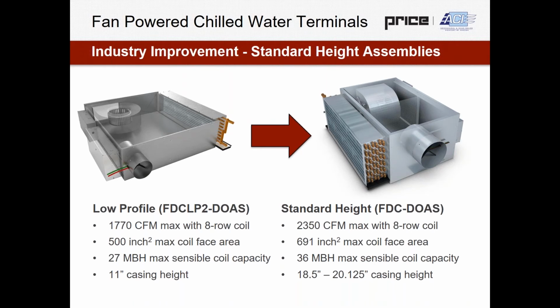For those of you who maybe aren't familiar with the history of this equipment, it was originally established and created for the Washington, D.C. region, which has some really strict building codes, especially in regards to building height. Nothing can be taller than the Washington Monument. So that results in a minimized floor to ceiling height and a minimized plenum height. And essentially the original piece of equipment, the low profile box on the left, was created for that market with the intent of a series fan-powered layout with chilled beam efficiency and performance.